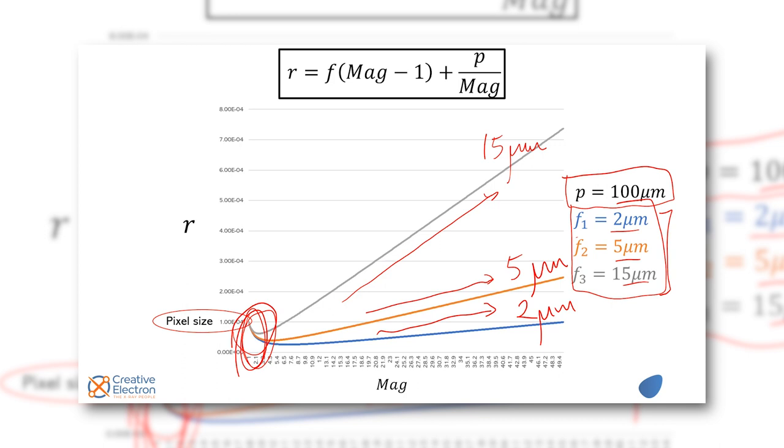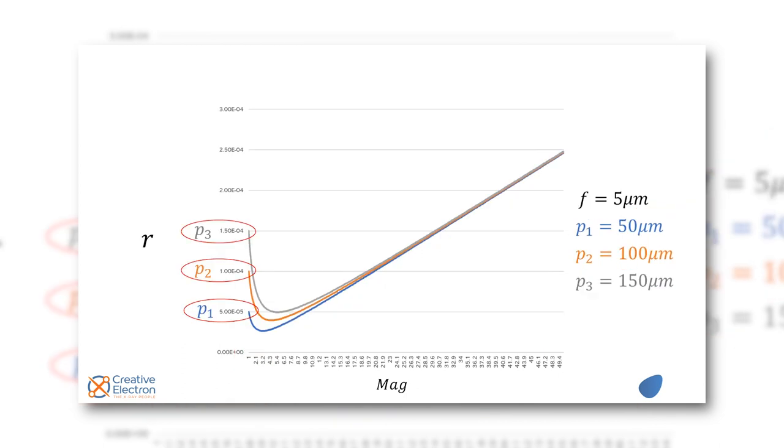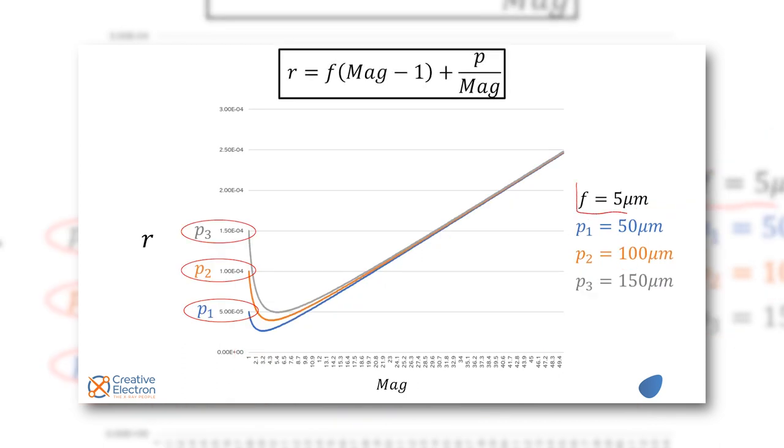So let's do the opposite, let's now pick one focal spot for the x-ray source and play with different pixel sizes. We have pixel size blue is 50 micron, orange is 100 micron, and gray is 150 microns. Just like we saw before, I love how these things all come together intuitively. The pixel size has a deep impact on low mag and not a major influence when you have high mag.